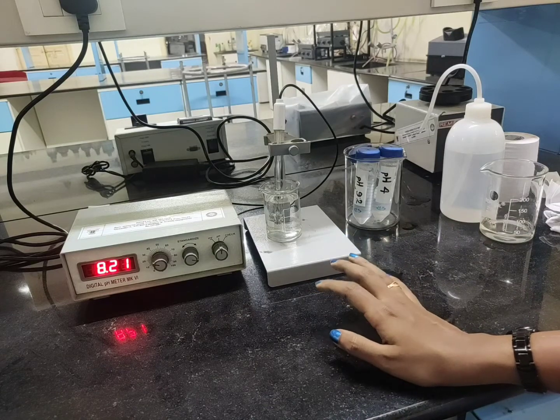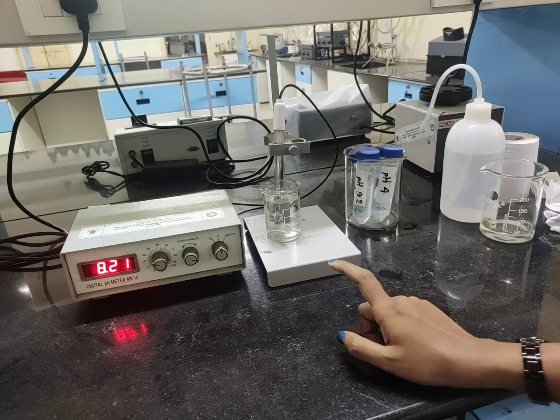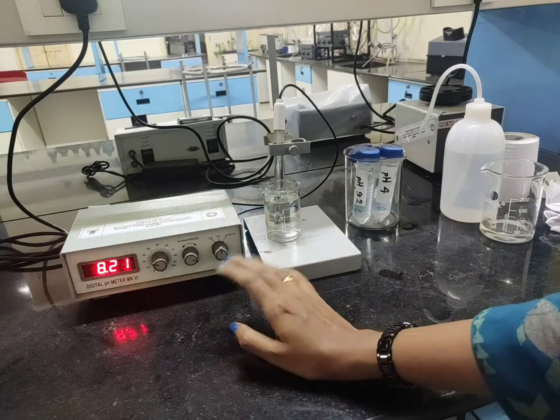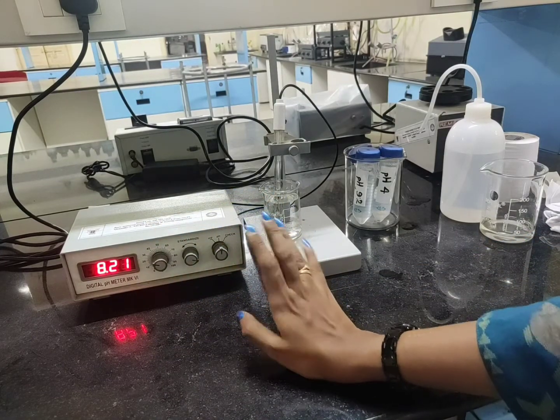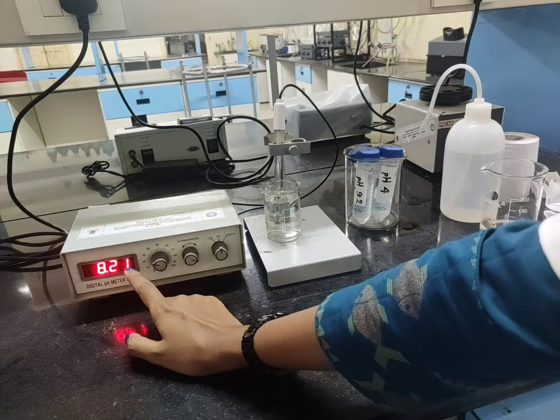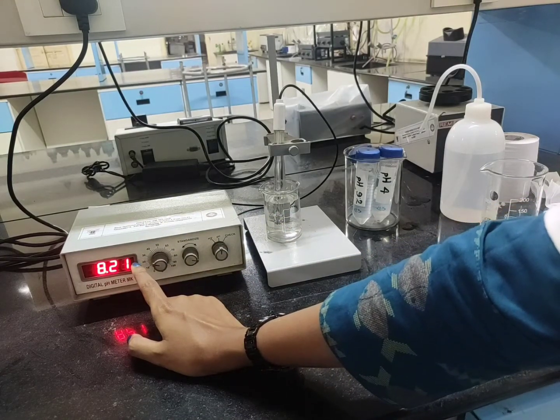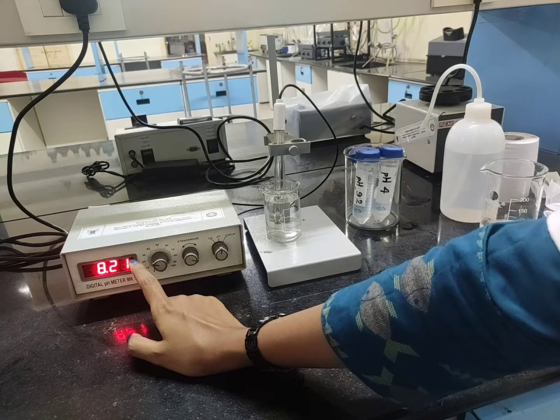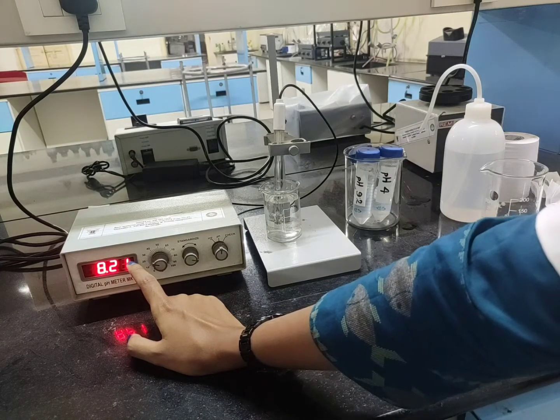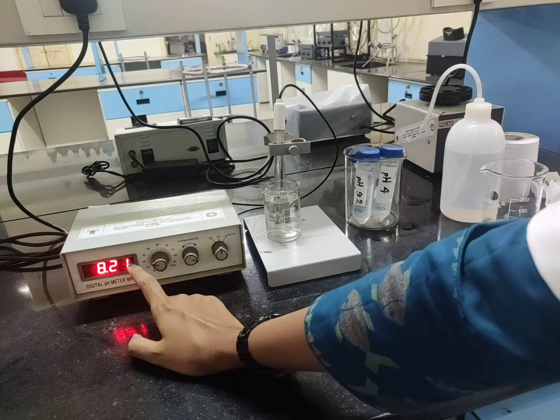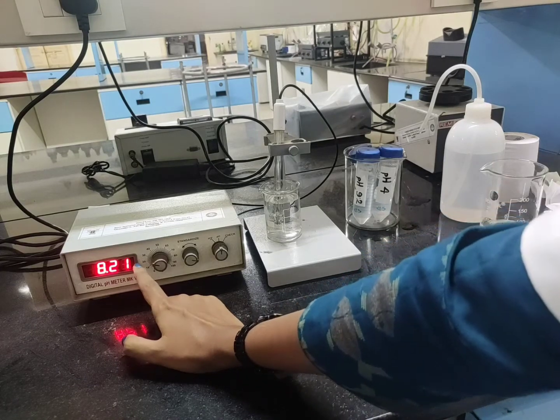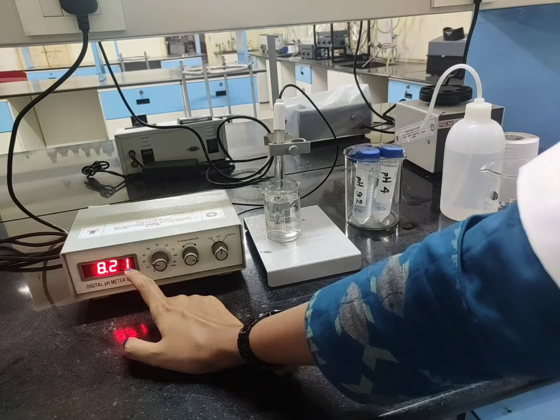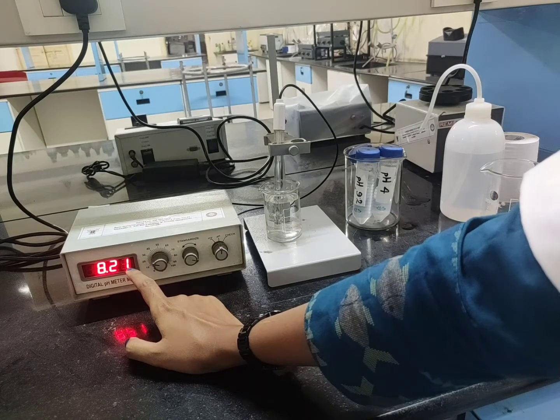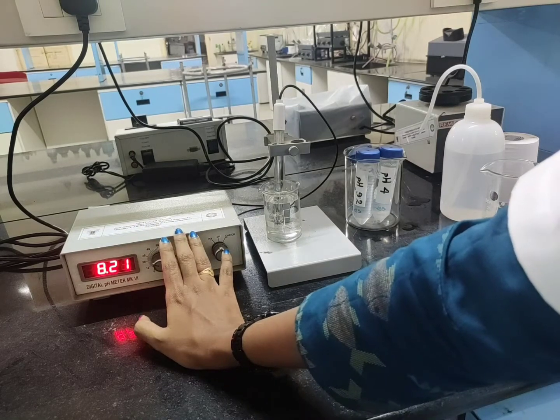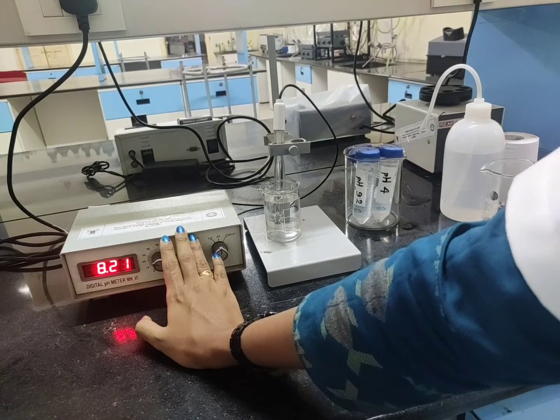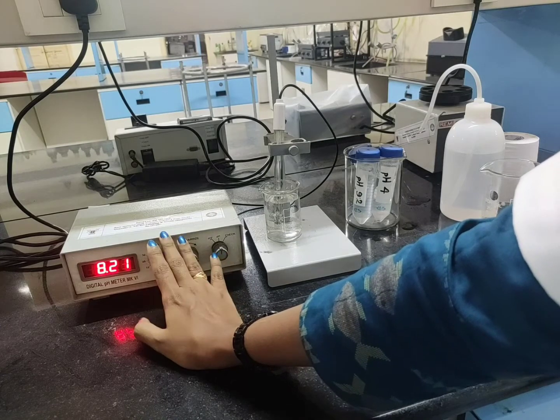Then the other very important thing while taking the reading of the instrument is that in whatever food sample or buffer you are putting your probe, you have to see that the reading comes stable for at least 2 to 3 seconds. Sometimes it happens, even when calibrating, that if you have given 7 pH buffer and the instrument is constantly fluctuating from 6.9 to 7.1 or 7.2, in such cases don't use the instrument, because that means the instrument is not working properly. That's why you are getting so many fluctuations or variations in the reading.